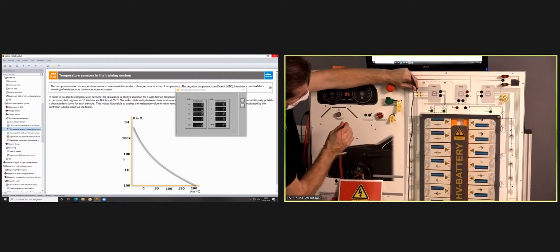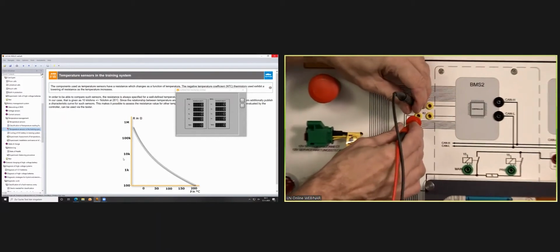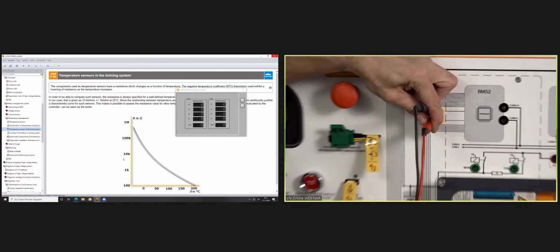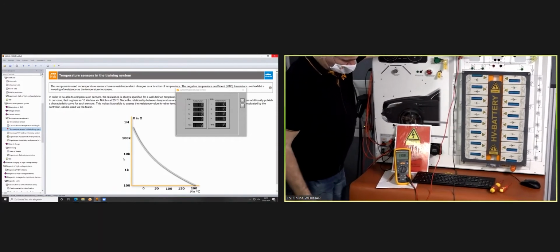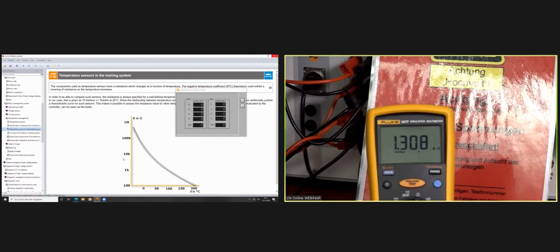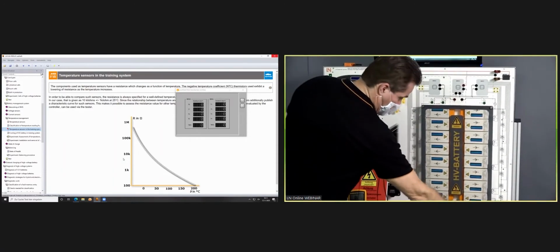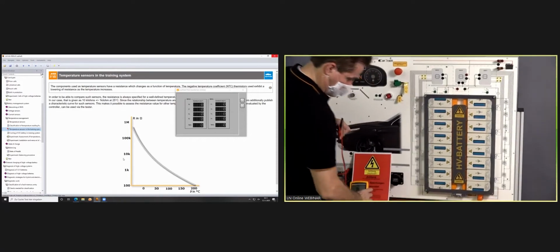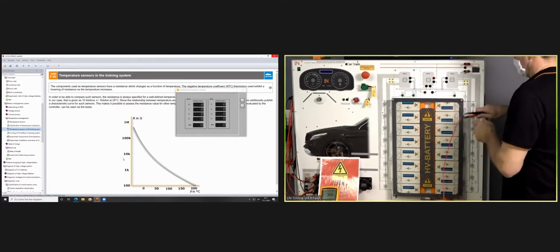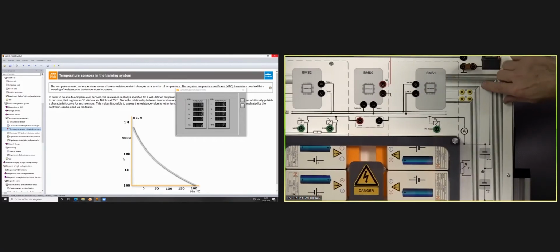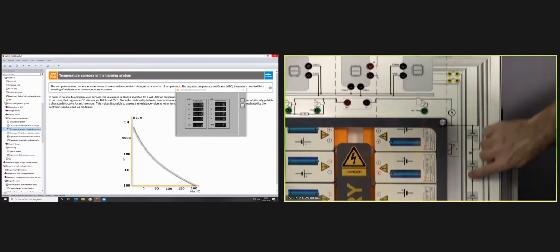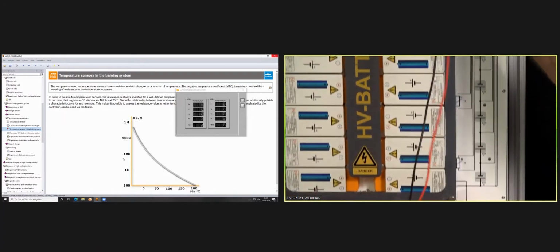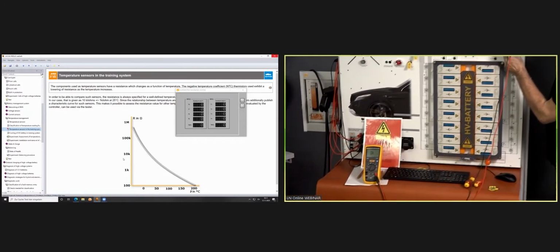So now I go to measure point X1 to X2, measure directly during the wiring up to the sensor, and now I can see the resistance in the sensor. There's a second possibility, I can choose a second sensor. There's a second wiring, and I can measure the other one over there. We have in total 8 sensors. The second sensor goes here, and there was no complaining about this sensor, so this is my reference.